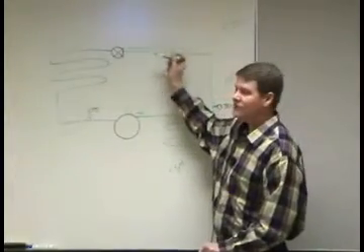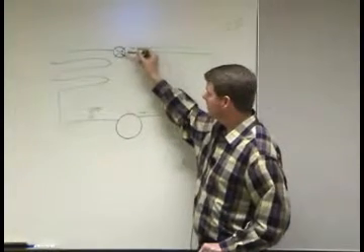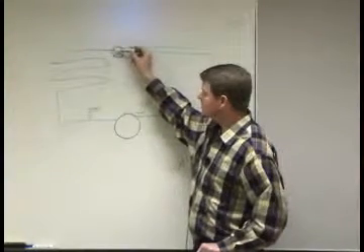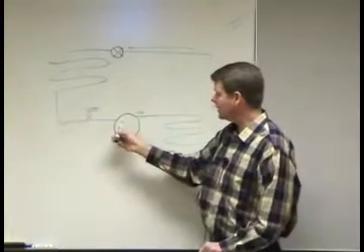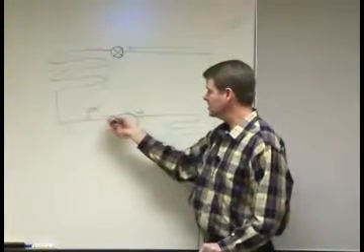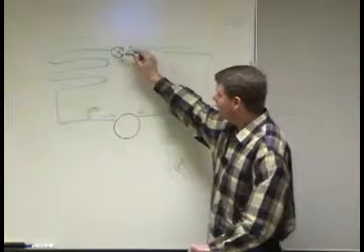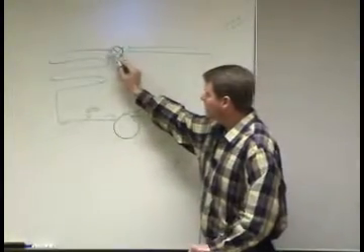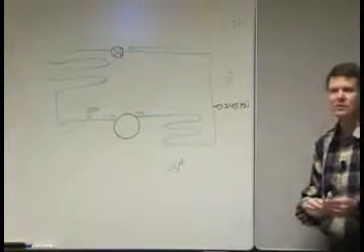We got this 245 pound liquid coming into here, and it goes through this restriction, and as you see, we're piped back to the compressor, which is, of course, sucking as well as blowing. So we put this restriction in here. Now on this side, the blue side, we're going to reduce the pressure down to like 75 pounds.